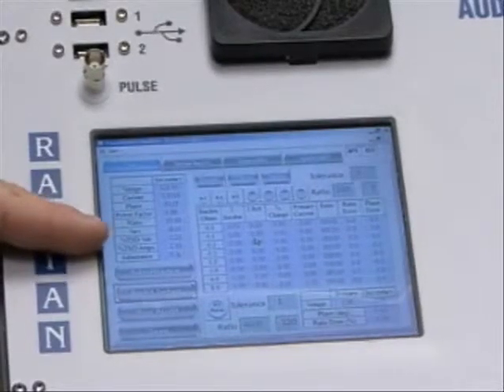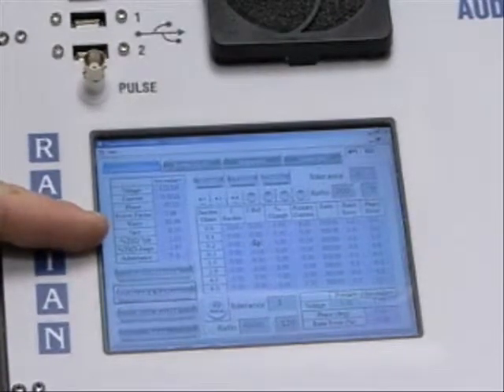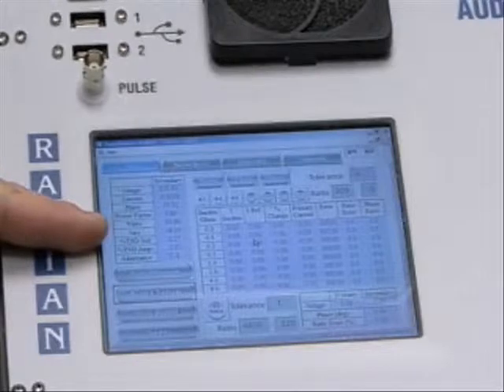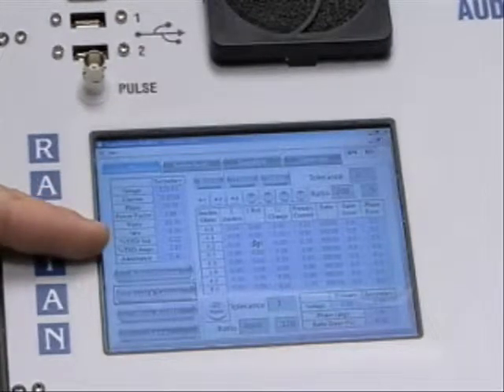A nice measurement that we show on the TX Auditor is the total harmonic distortion for the voltage and the current. The total harmonic distortion for the voltage is 2.25%, and the total harmonic distortion for the current is 2.1%.